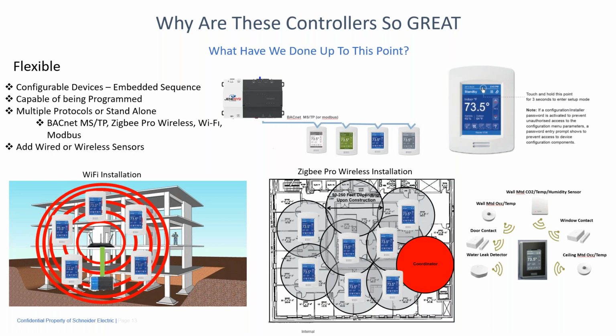So in the lower left-hand corner, there might be a Wi-Fi installation where I'm taking a standard Wi-Fi router. Wherever that casts out its signal, each one of the controllers can join that network, and then that goes BACnet IP to your supervisory device. In the center bottom portion here, we've got a Zigbee Pro wireless installation where you've got each one of the controllers cast out their bubble, and then there's a coordinator device which we provide, and each one of those guys communicate with that coordinator. Coming out of the coordinator is BACnet IP. That's a self-healing mesh network. So if one of the devices would go down for repairs, let's say, or maybe there's a problem, the controllers automatically find their path back to the coordinator, so you don't have to worry about setting up any sort of communication network.